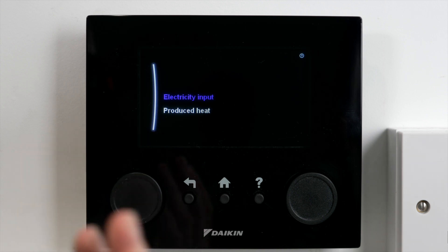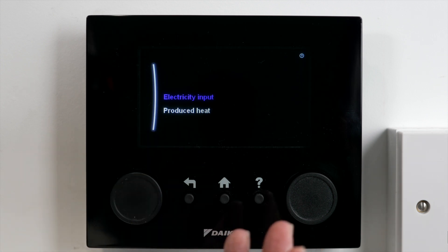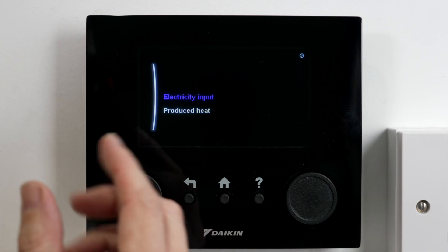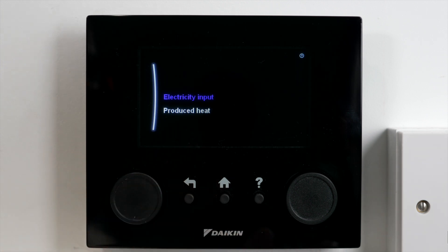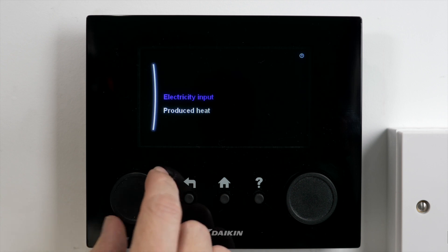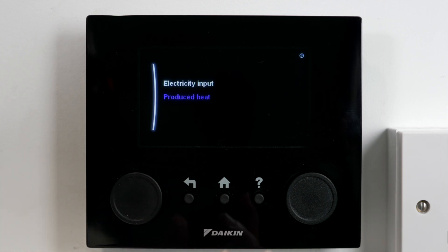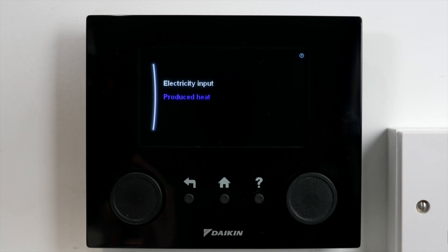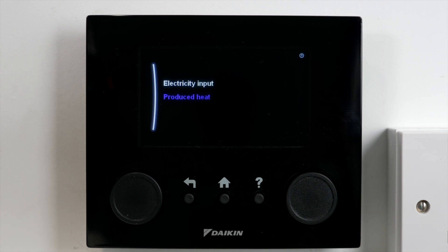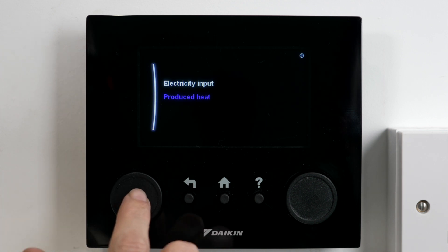Click into there and it's going to give me electricity input and the amount of heat that the unit has produced. I'm going to go to heat first, because to work out your COP you want to do your heat in kilowatts divided by your electricity input in kilowatts, and that's going to give you your COP number.